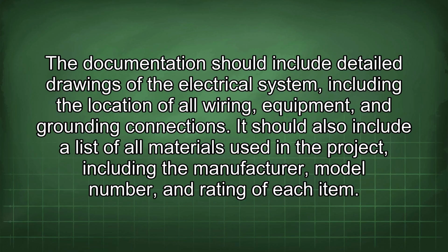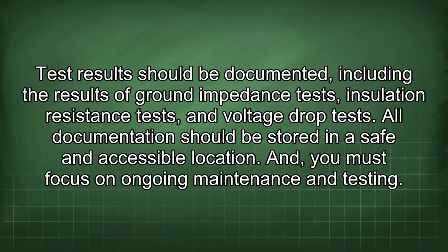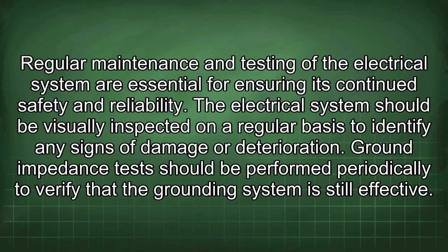of each item. Test results should be documented, including the results of ground impedance tests, insulation resistance tests, and voltage drop tests. All documentation should be stored in a safe and accessible location. And you must focus on ongoing maintenance and testing. Regular maintenance and testing of the electrical system are essential for ensuring its continued safety and reliability.